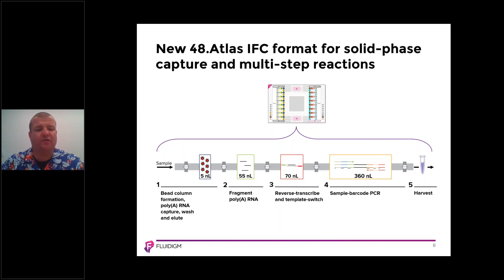A key point is that though these valves are independently controlled, once one step is complete, the subsequent steps take place across all reaction chambers. When we perform the sample barcode PCR, it takes place across steps three, two, and one. Though we're working with very small volumes, performing subsequent reactions across the previous chambers means nothing is left behind, maintaining high reaction efficiencies. Once all of that's complete on the IFC, the product is harvested into a single tube and follows the regular Illumina NGS workflow including purification, PCR, and normalization.